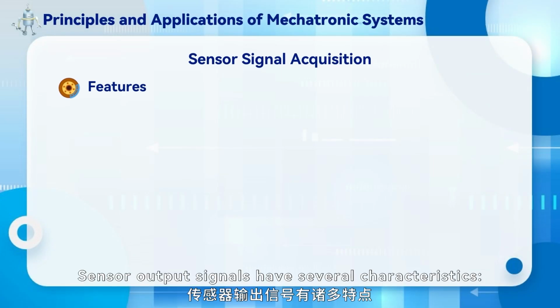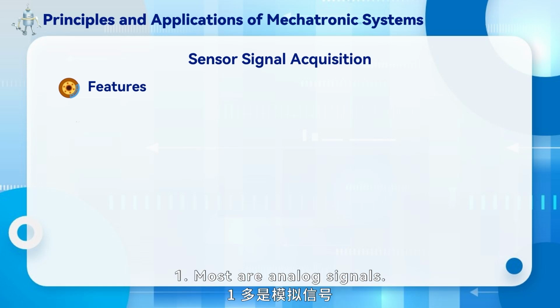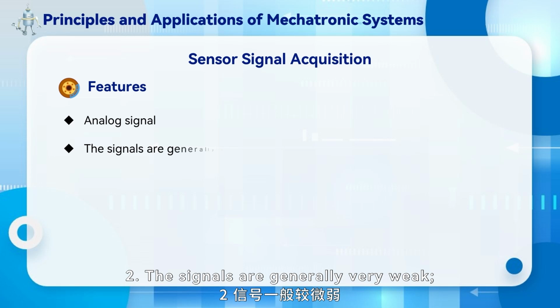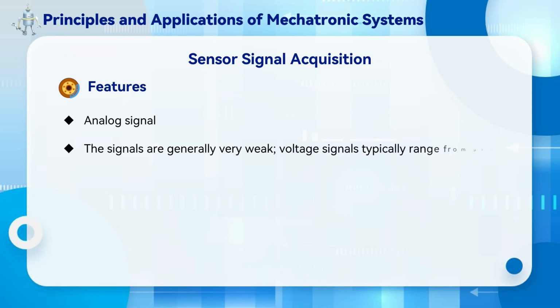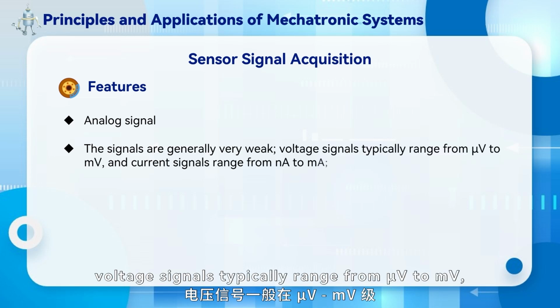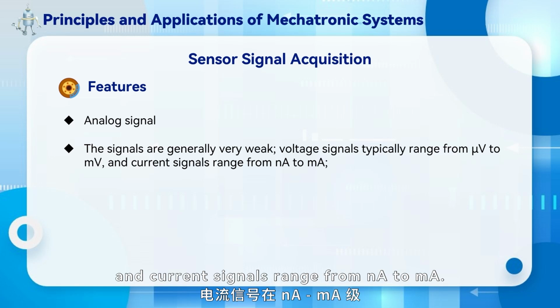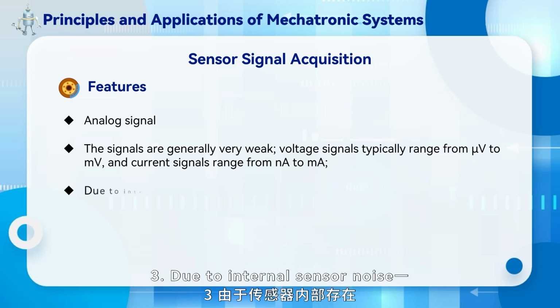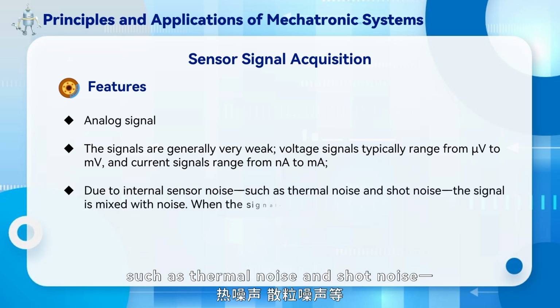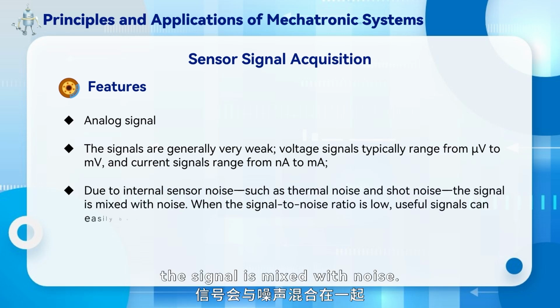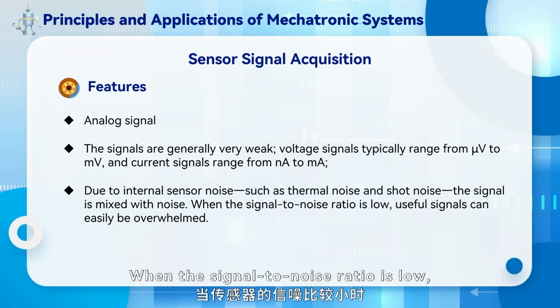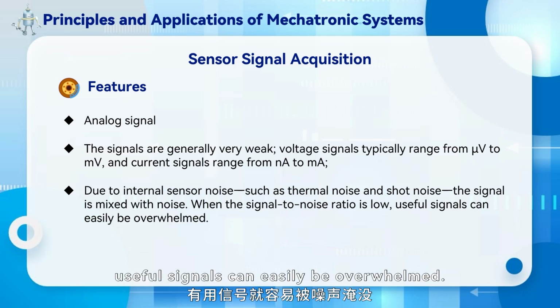Sensor output signals have several characteristics. 1. Most are analog signals. 2. The signals are generally very weak. Voltage signals typically range from microvolt to millivolt, and current signals range from nanoampere to milliampere. 3. Due to internal sensor noise, such as thermal noise and shot noise, the signal is mixed with noise. When the signal-to-noise ratio is low, useful signals can easily be overwhelmed.